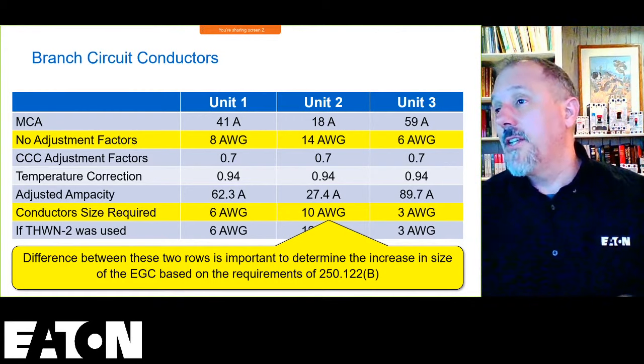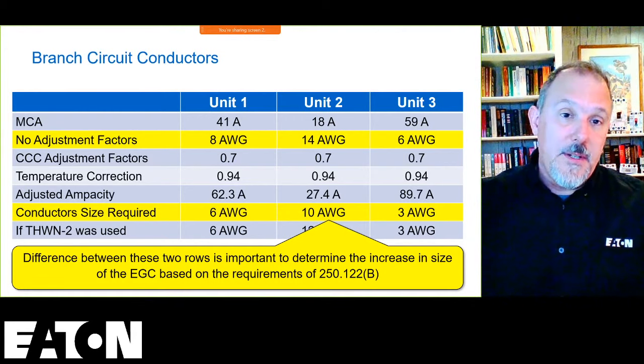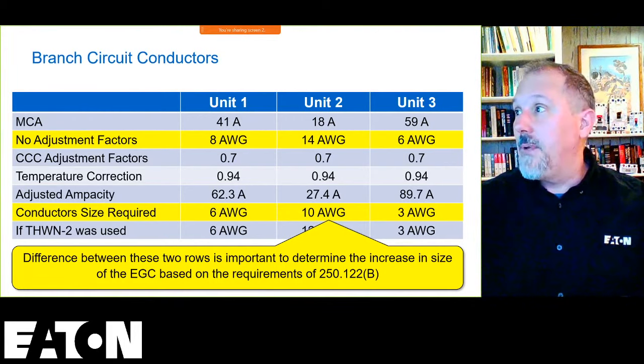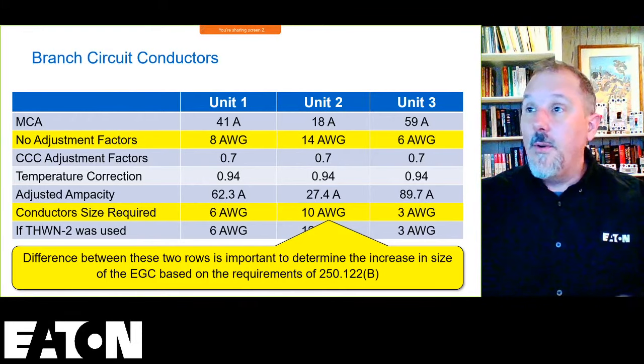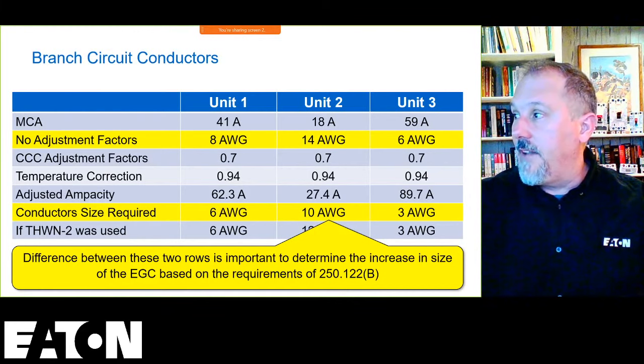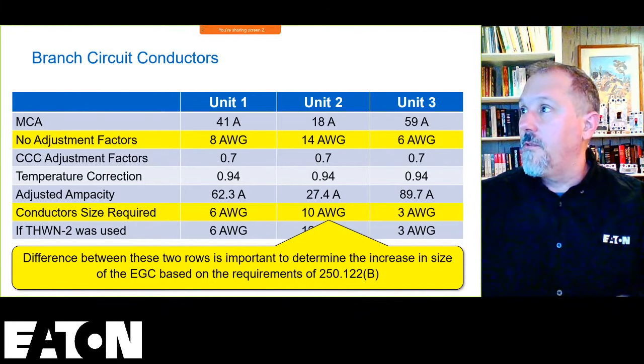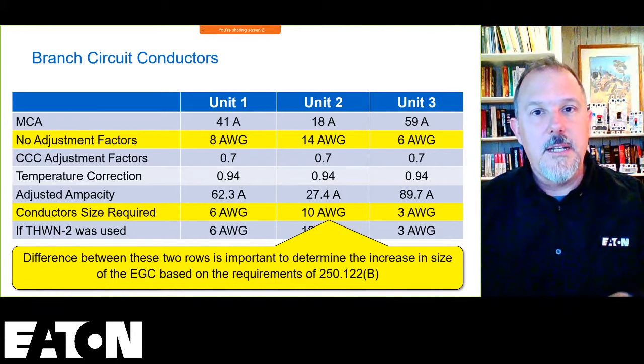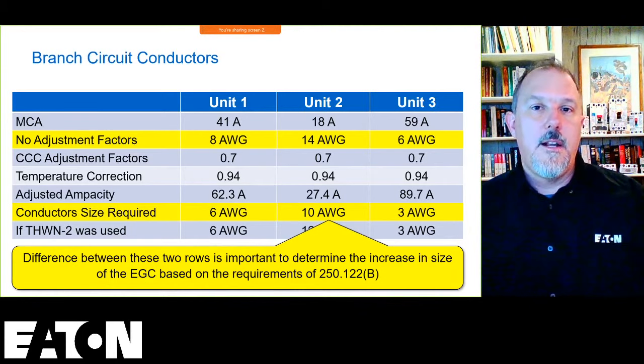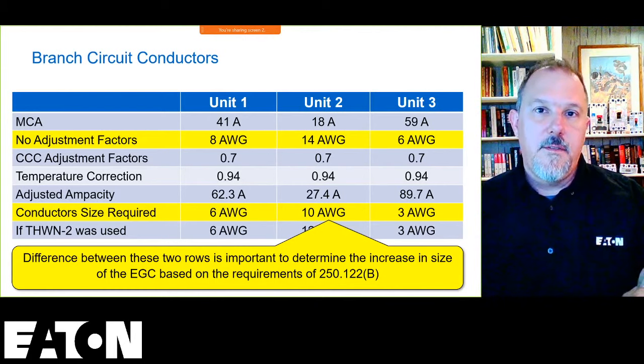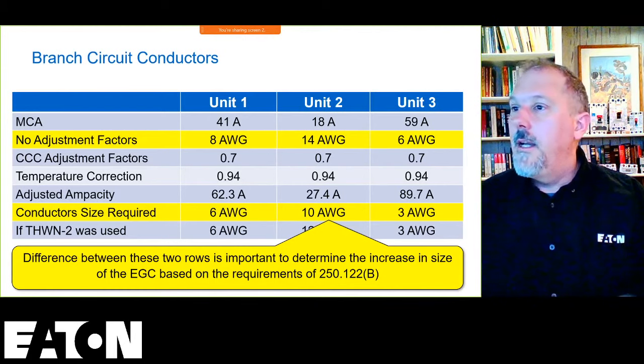So what I did now, I did the increase in size of the equipment grounding conductor. If I don't do any adjustment factors, I'm at an 8, but I have a number 6, I have a number 10, I have a number 3. But we pick the equipment grounding conductor size based upon the overcurrent protective device, not the size of the ungrounded conductors, right?